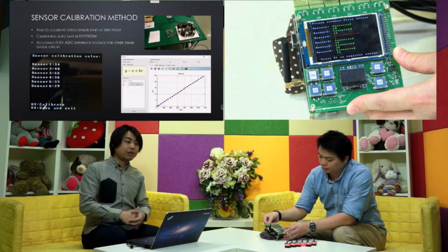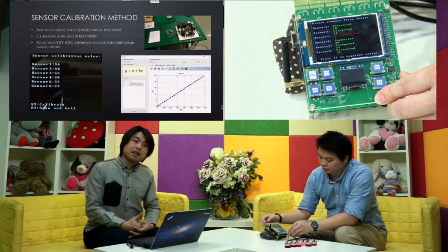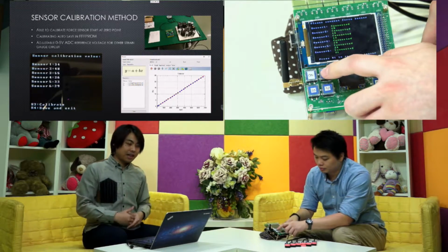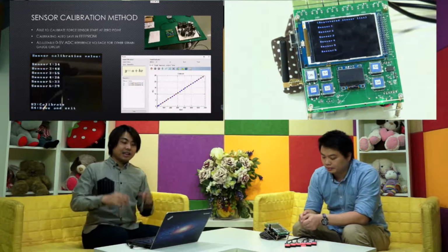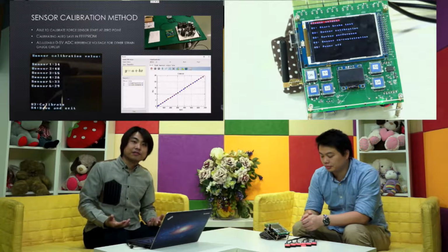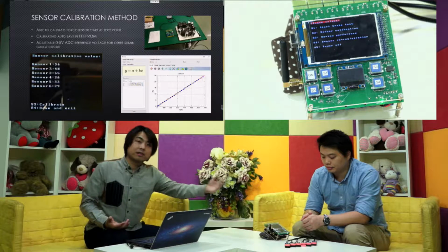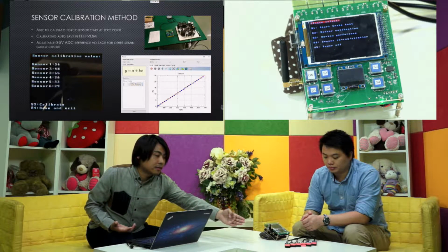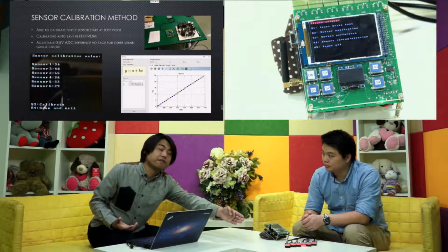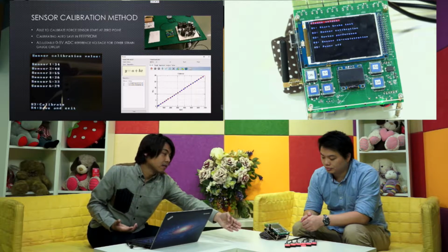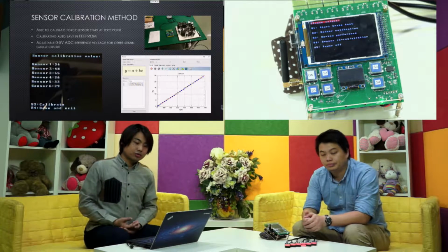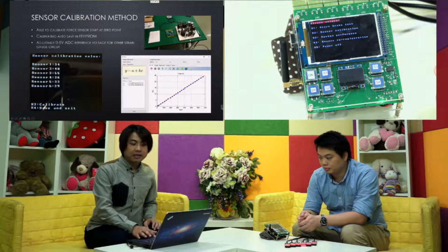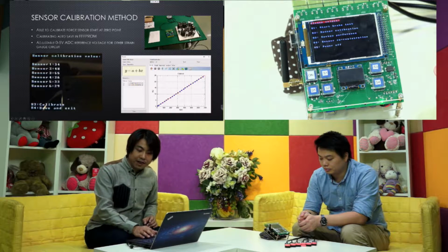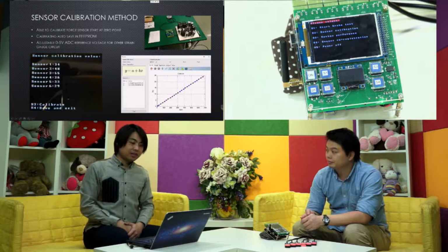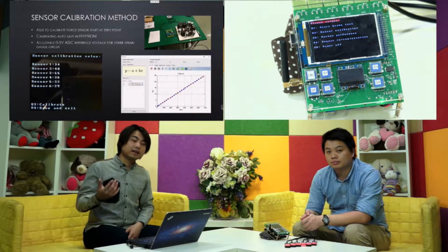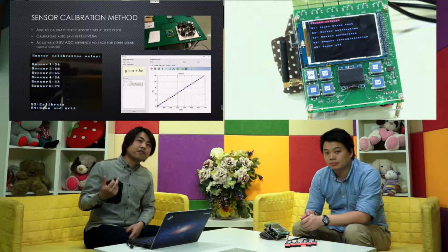Okay, now we want to talk about the calibration method. From some tests, we discovered that our strain gauge outputs a totally linear curve to the device. We adopted a 55 kg capacity for the sensor. We tried adding a lot of counterweights for testing and plotted the graph like that. This is totally linear. So the sensor calibration problem is how to define the 0 point.